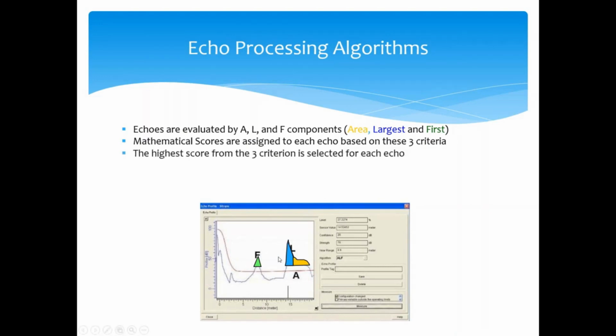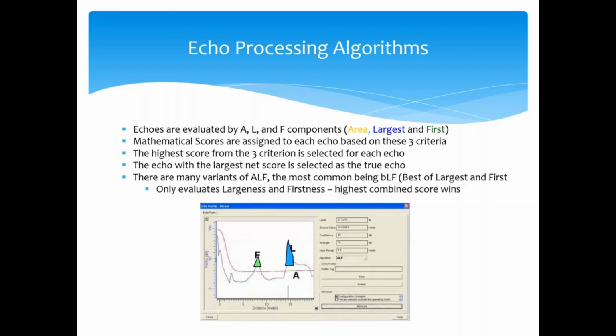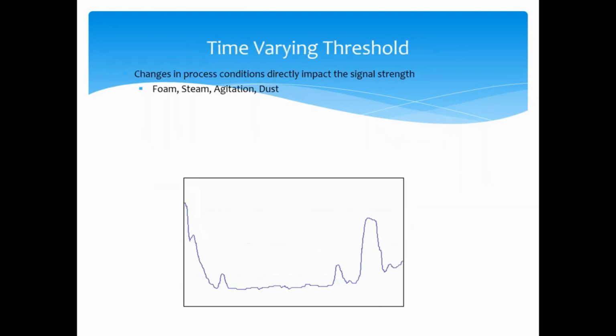For a more common application, we're going to look at a combination of these 3 criteria, which we call ALF, which is area, largest, and first, based on different criteria, whether we're the first echo, the largest echo, the area above the echo. Every echo gets assigned a score, and the signal with the highest score is what we consider to be true liquid level. So in this case, this is the second signal return above the threshold, but based on the algorithms, it's the one that we choose to be true liquid level. So this might be, you know, a ladder, a float ball, something causing signal return, and then this is our true liquid level below that. As far as choosing your algorithm, typically just leave it in the default, and if you have any issues or specific questions about an application, you can talk to one of your Gilson sales people, and we can help select the proper algorithm for you.